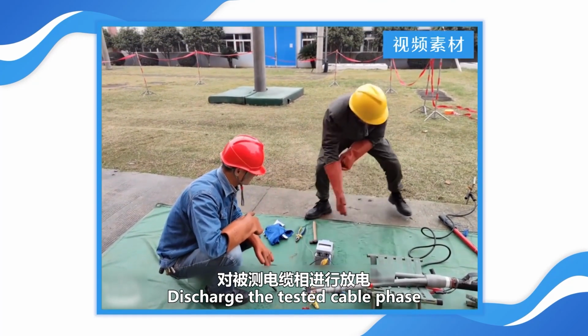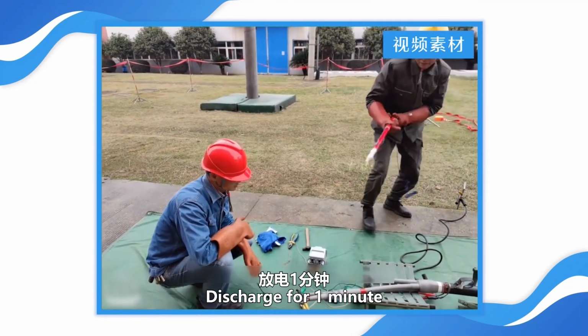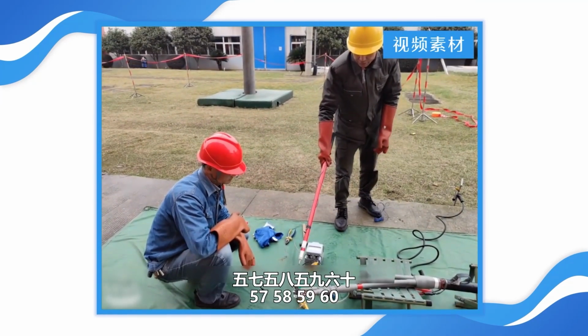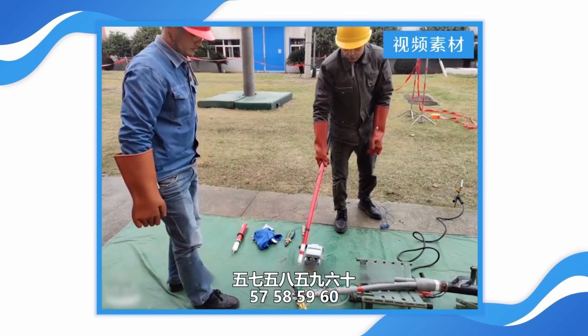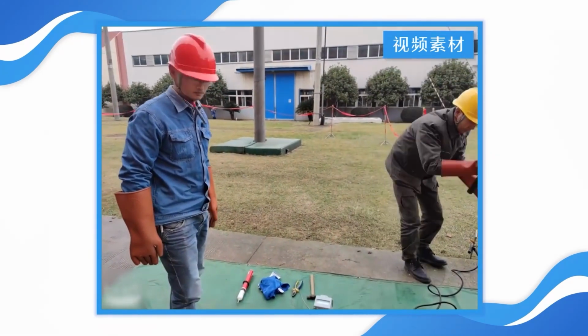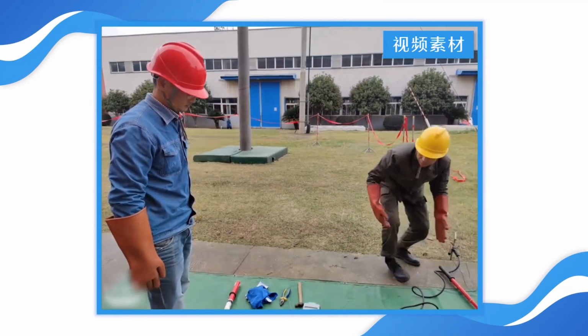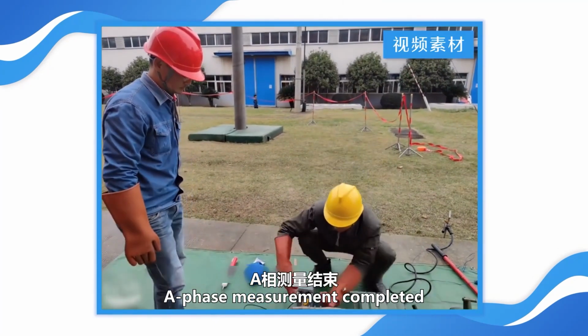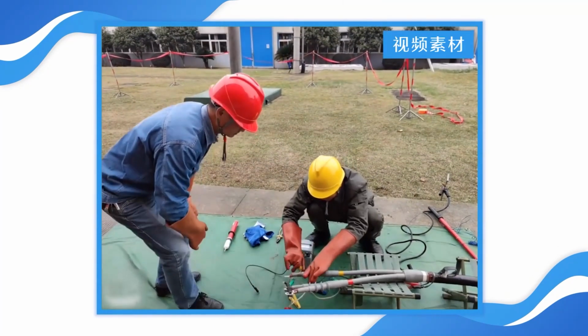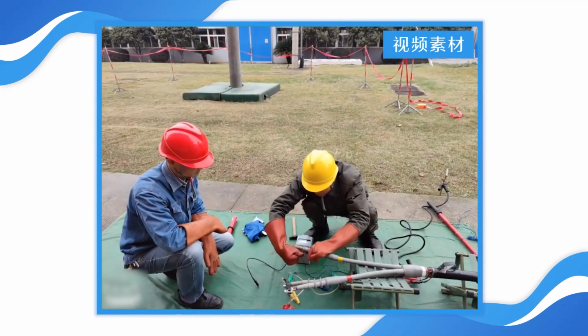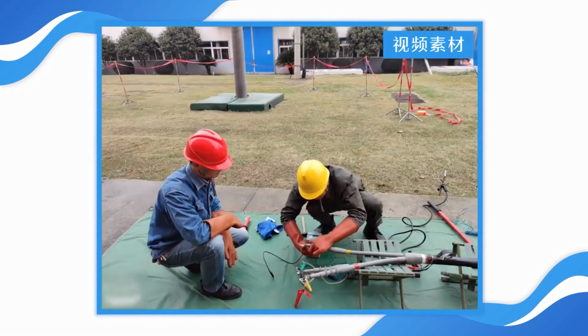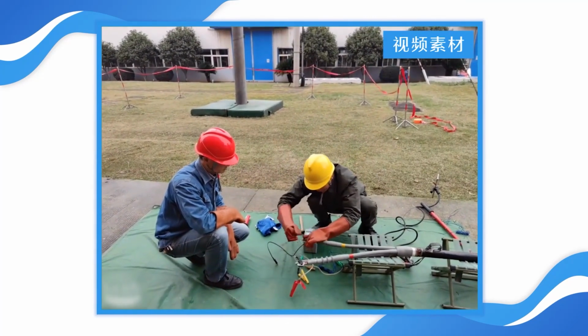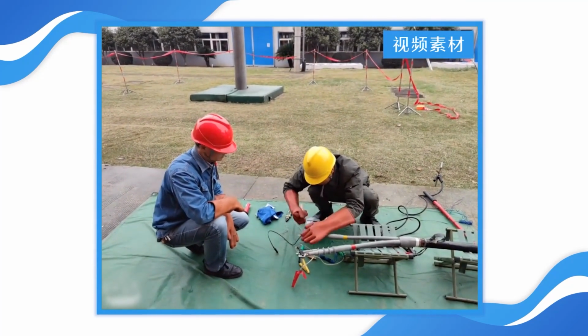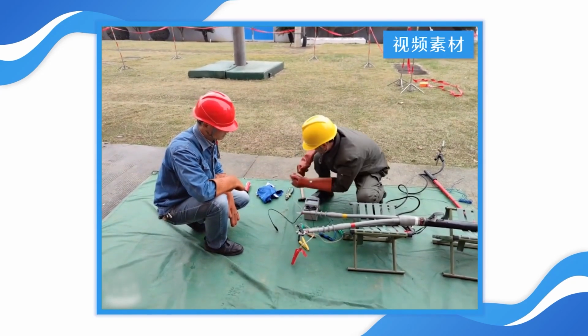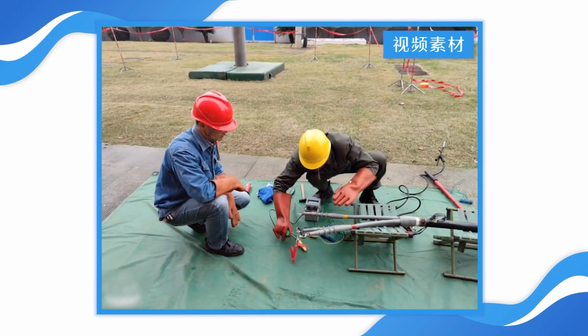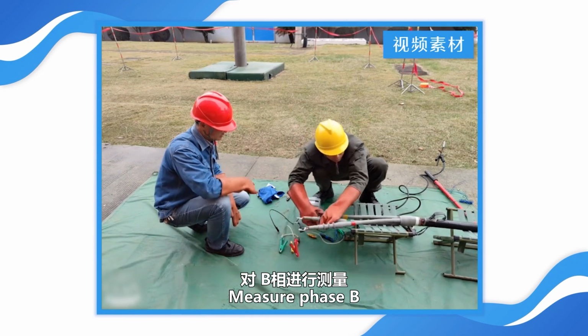Discharge the tested cable phase. Discharge for 1 minute. 57, 58, 59, 60. A-phase measurement completed. Measure phase B.